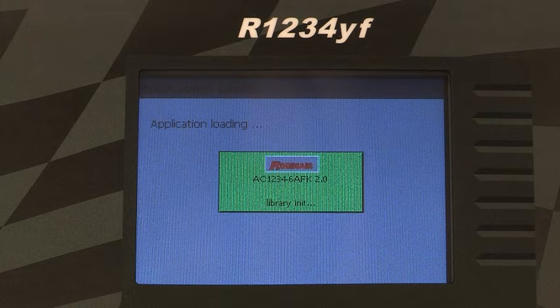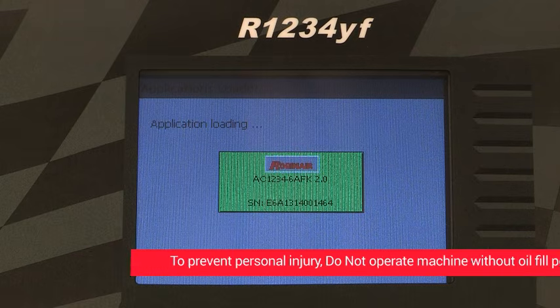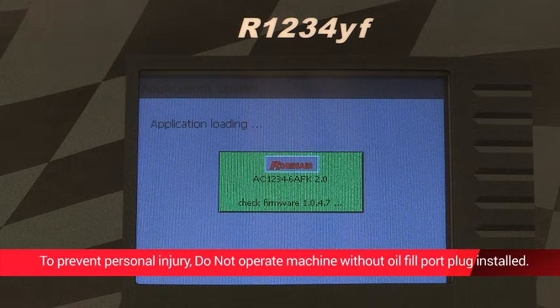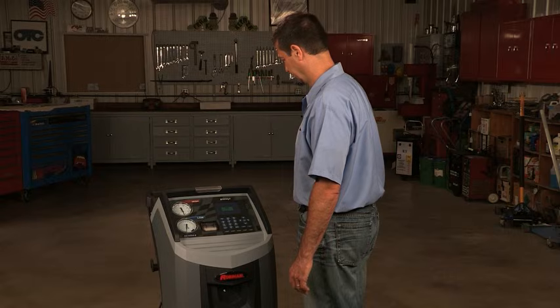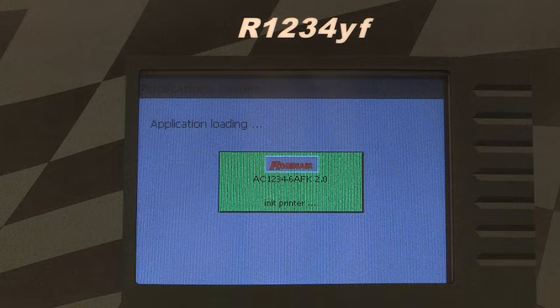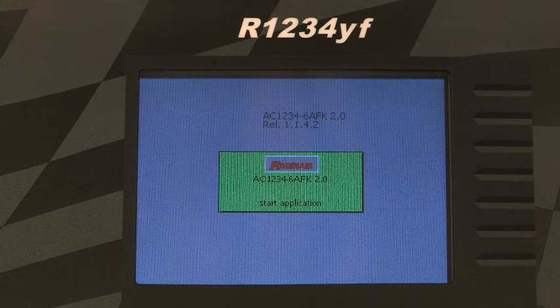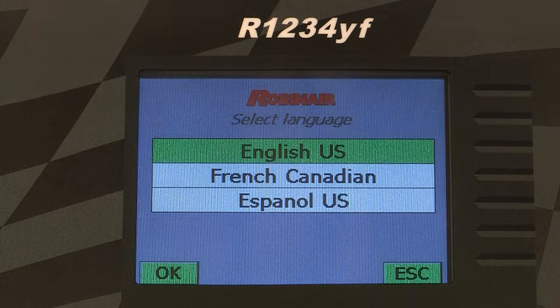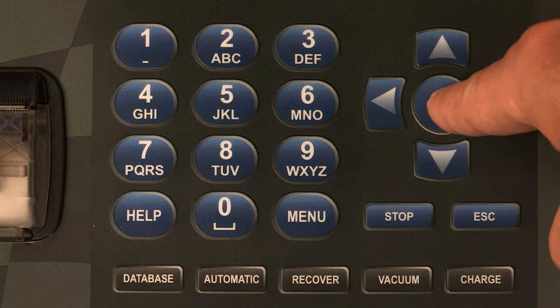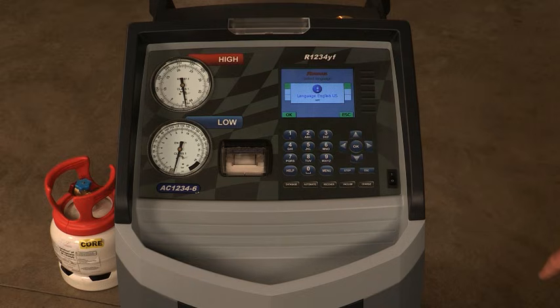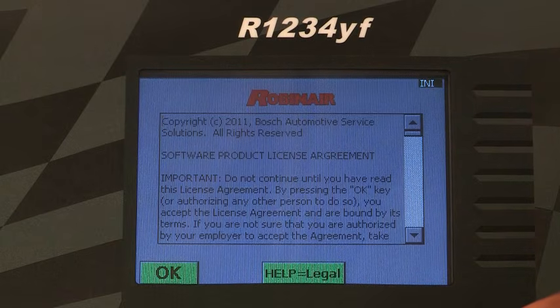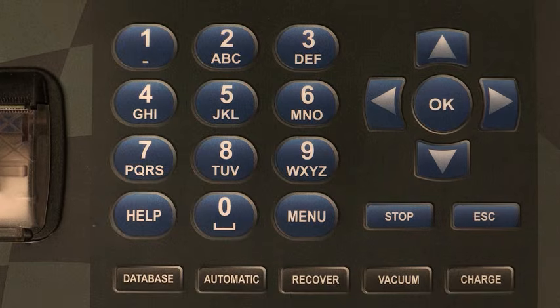It is important to note that the machine is programmed to run the setup procedure as outlined in the owner's manual. To prevent personal injury, do not operate the machine without the oil port fill plug installed, because the vacuum pump is pressurized during normal operation. The operator needs to select the language from the screen prompt displays. English is the default language. Use the up or down arrow key to toggle through the available languages. Press OK to set the selected language. The license agreement is displayed for your approval, after which the machine continues with the setup mode.